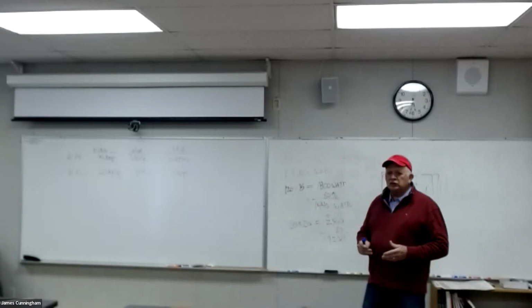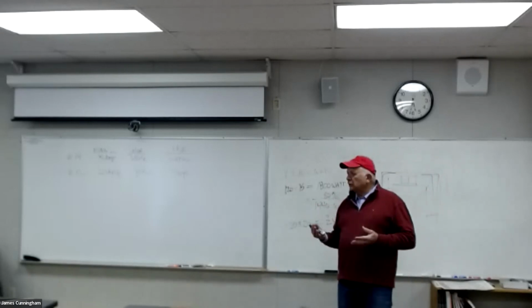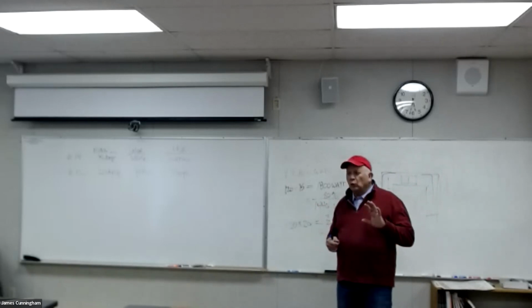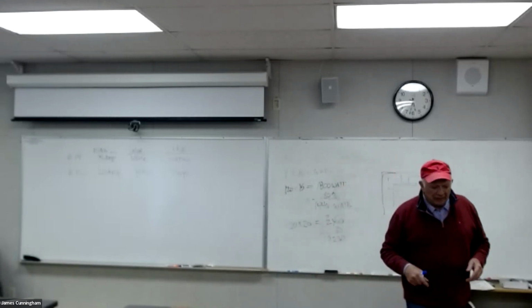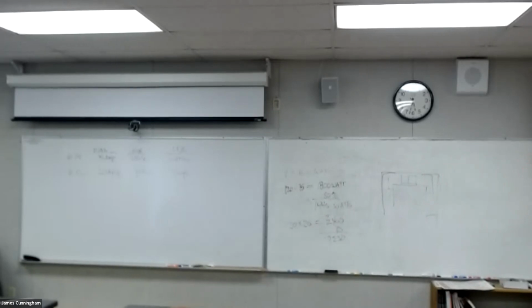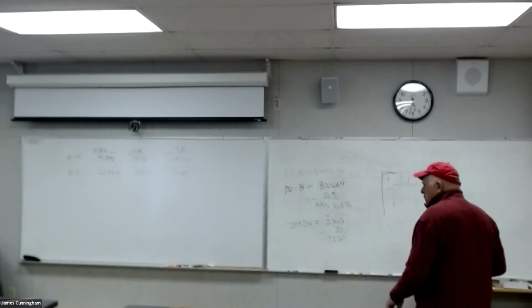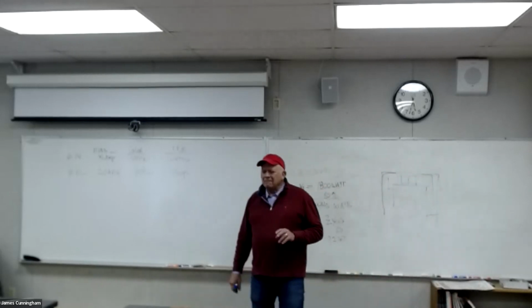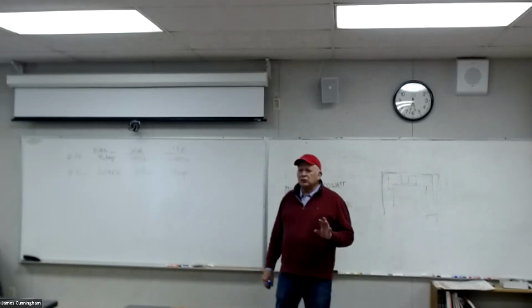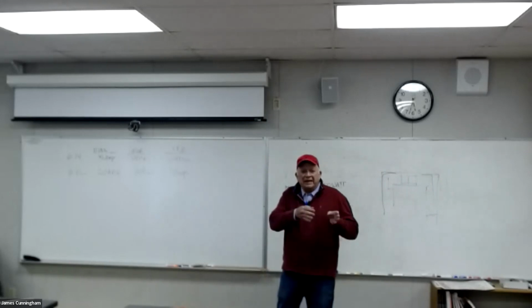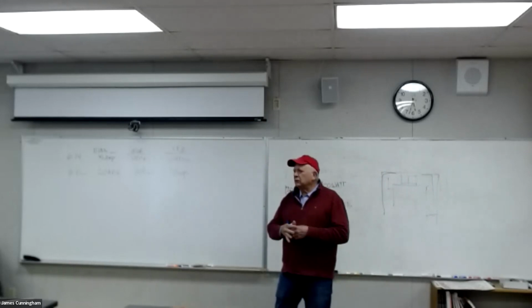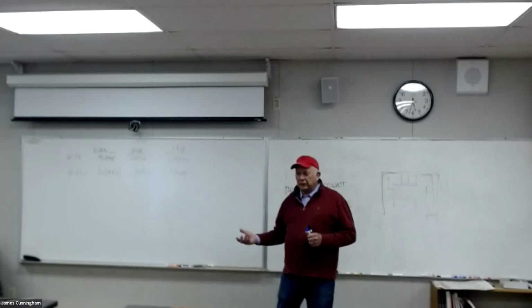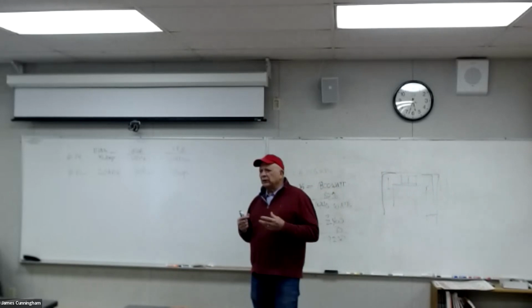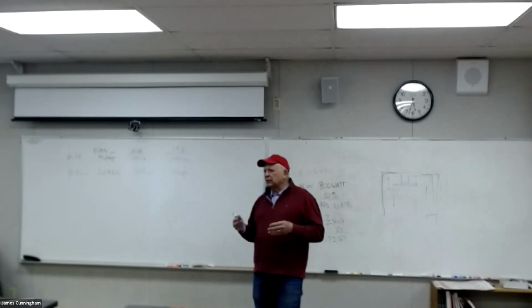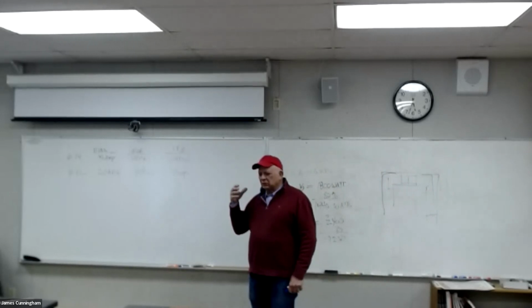Onward and upward. If you remodel a kitchen, a lot of times you have to upgrade your electrical service, because in the older houses, they only had like 8 or 10 circuits in the panel. If I only saw that I had 10 circuits, new kitchens usually require a minimum of 8 circuits, maybe 10 to 12 circuits. So if you only have a panel that takes 10 and you're already using 10, maybe 2 of them for the kitchen, you're going to have to upgrade your service to add more circuits just for the kitchen. So a lot of times when we're doing a kitchen remodel, we also have to do a service upgrade just to get enough circuits in the panel.